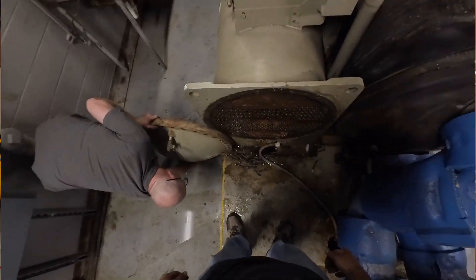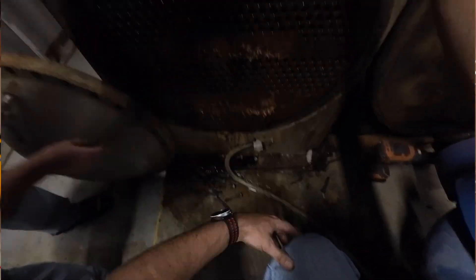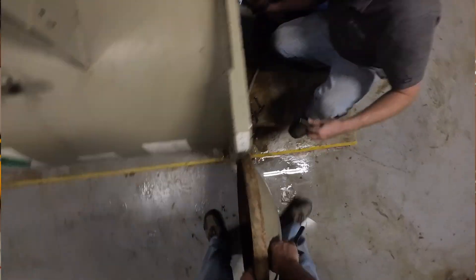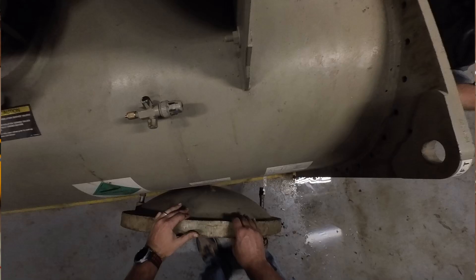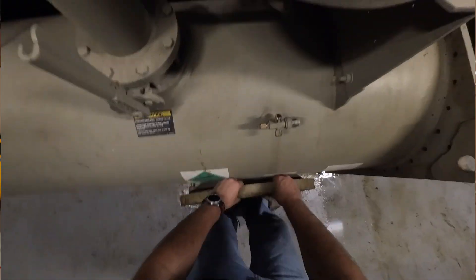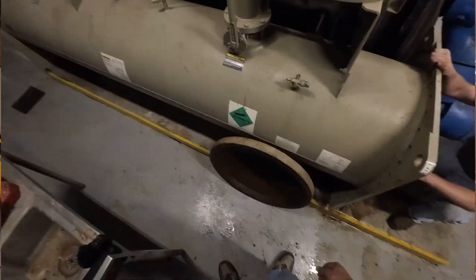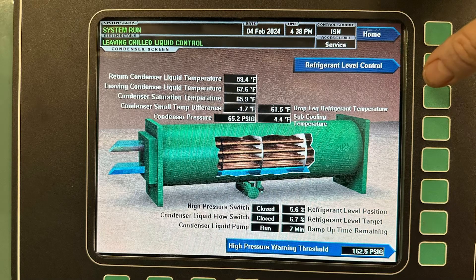If you walk up to a centrifugal that's having trouble with surging, this is a really quick first place to start. Most of your HMIs — your human interfaces on the chillers — are going to have the approach values given to you, so it's a very commonly measured item. However, not all machines will display it, so some you will have to calculate for yourself.